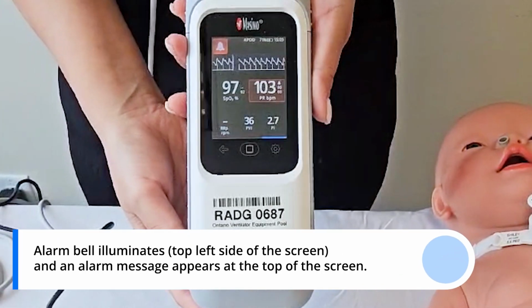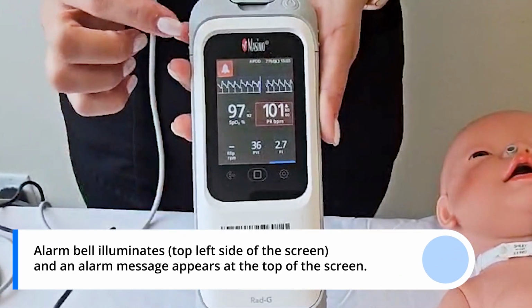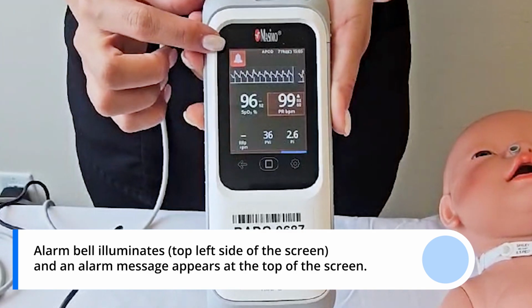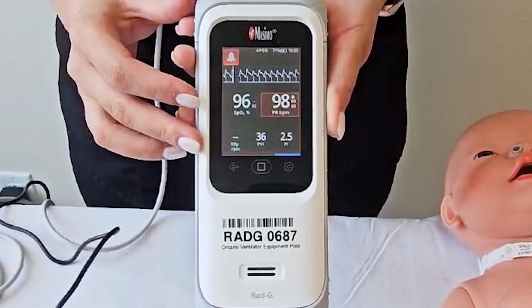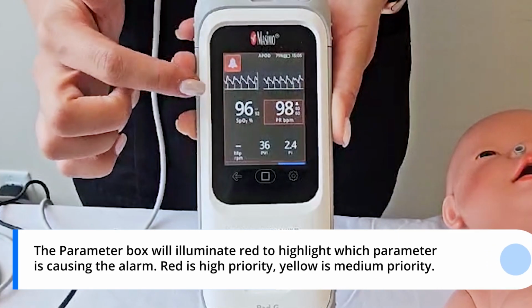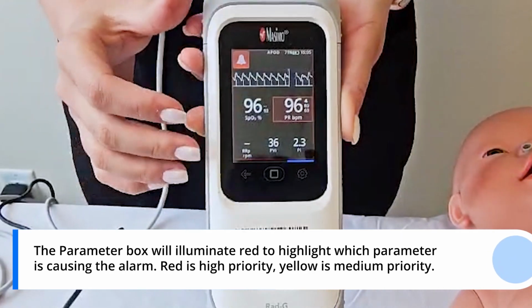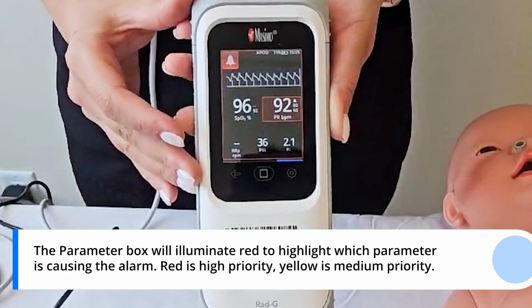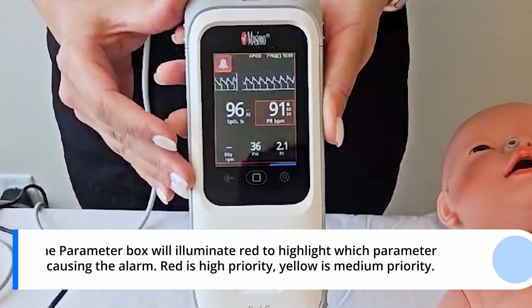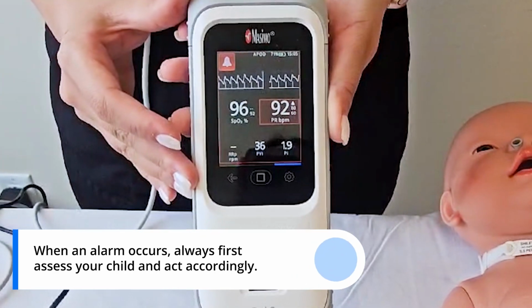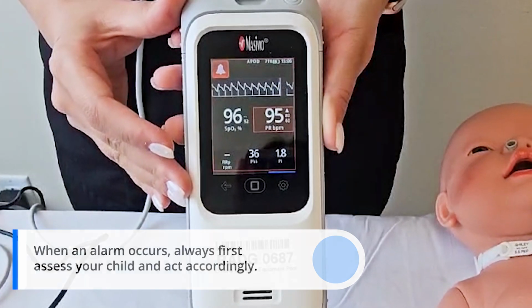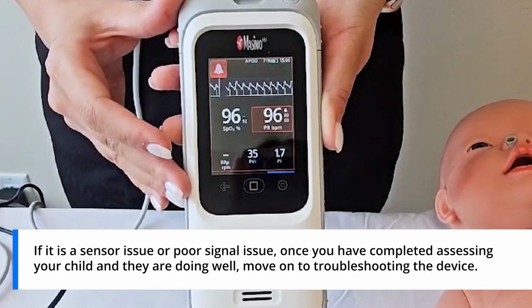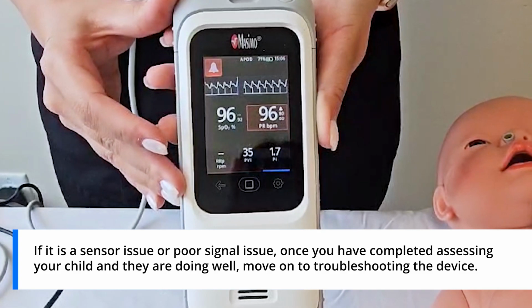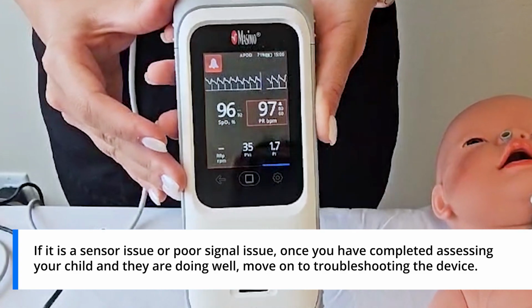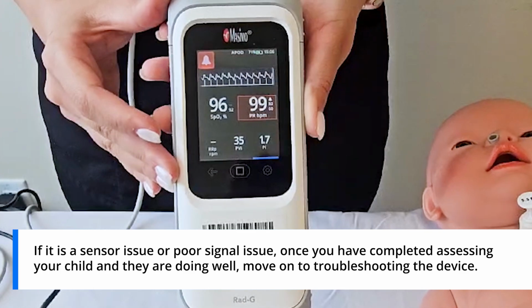The alarm bell illuminates on the top left side of the screen, and an alarm message appears at the top of the screen. The parameter box will also illuminate red to highlight which parameter is the cause of the alarm. Red is high priority, yellow is medium priority. When an alarm occurs, always first assess your child and act accordingly. If it is a sensor issue or poor signal issue, once you have completed assessing your child and they are doing well, move on to troubleshooting the device.